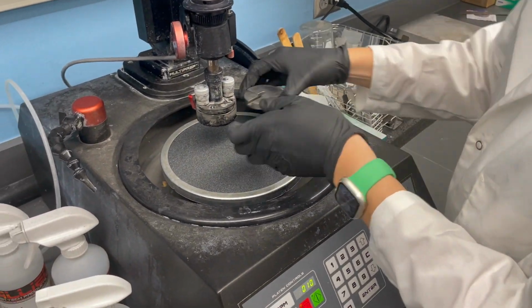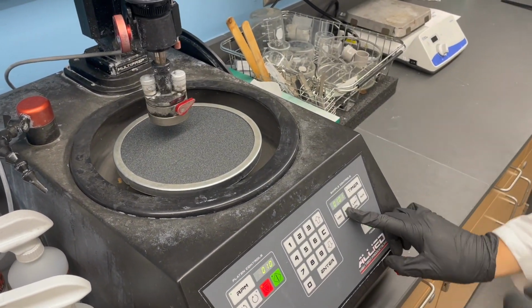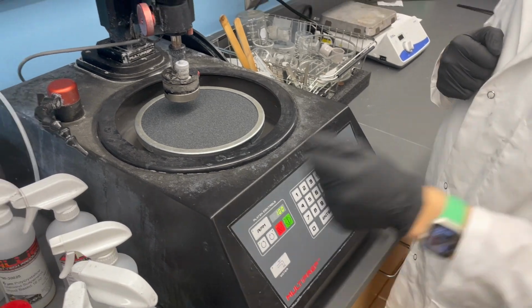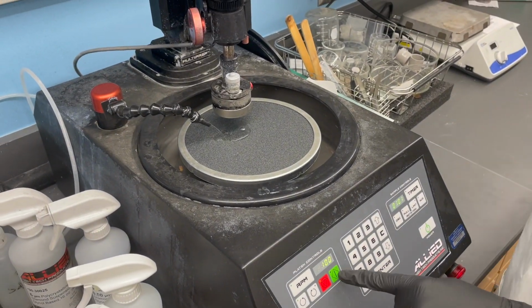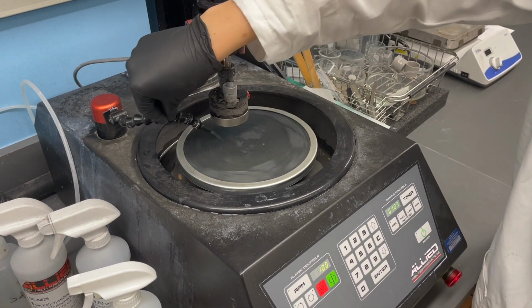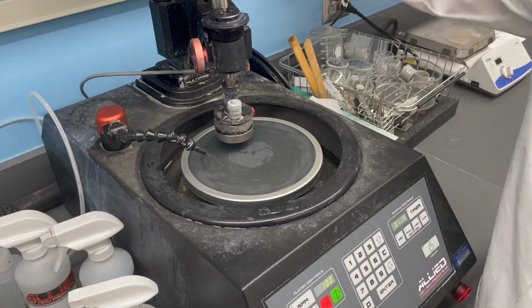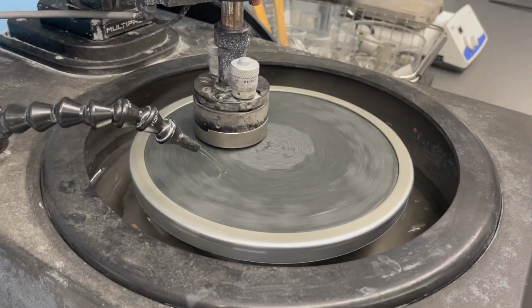Secure the paper with a silver ring. Take your cooled polishing fixture and attach it to the head with the red pin. Rotate so that the red pin is at 3 o'clock. Set the RPM to 100 and turn on the water to saturate your paper. Lower the head until the sample surface makes contact.